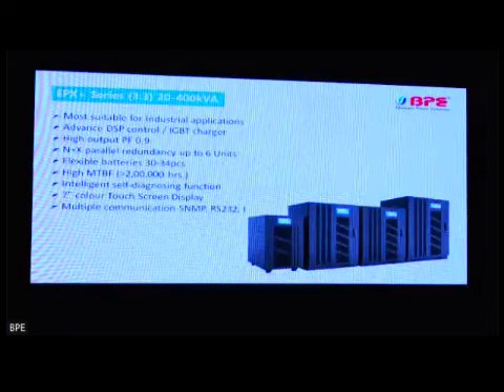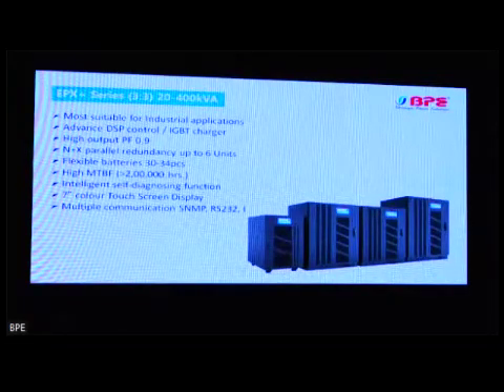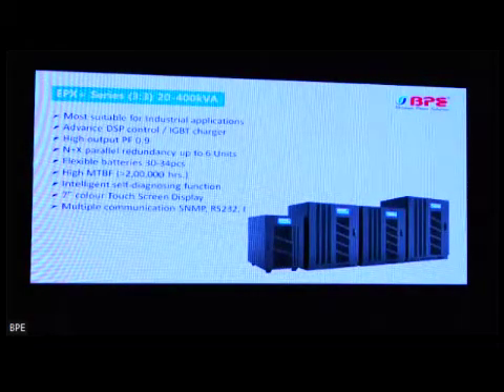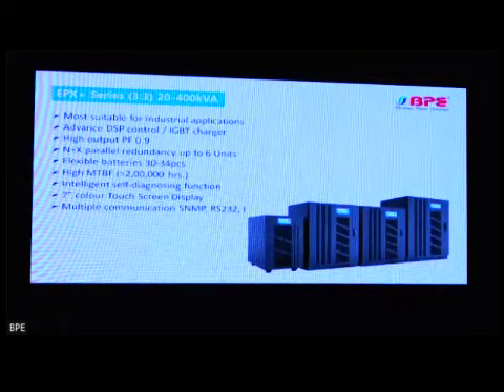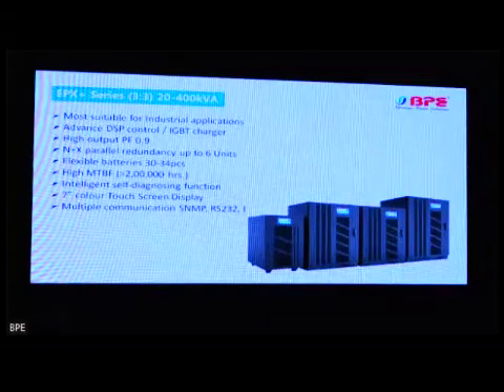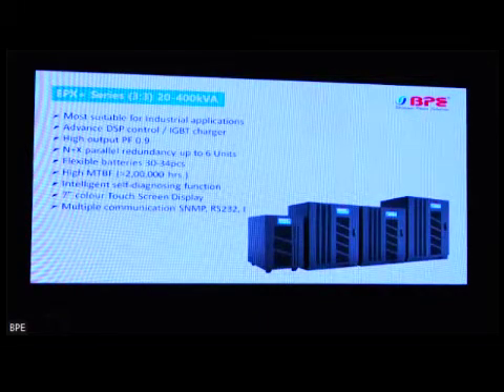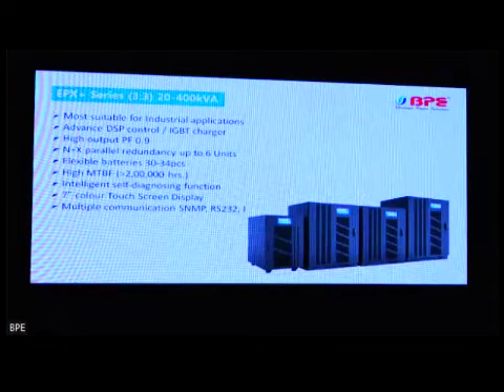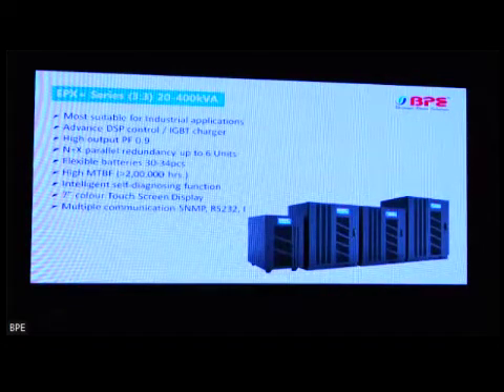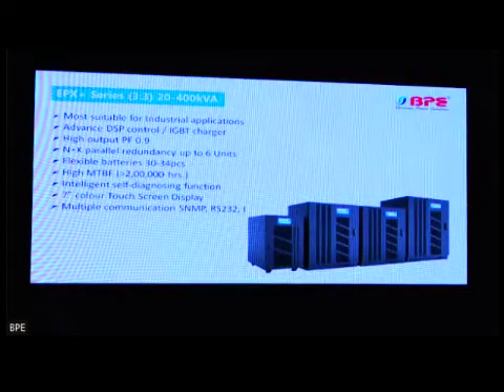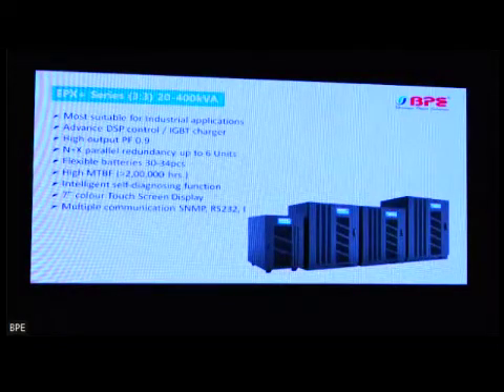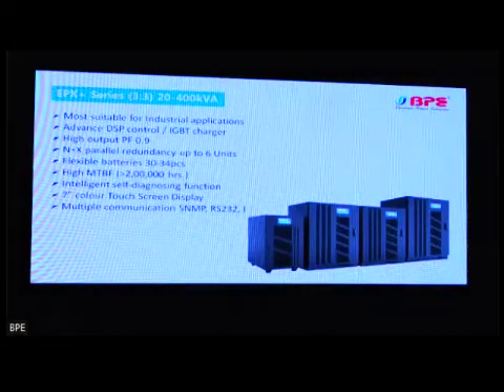Then we will have EPX Plus series starting from 20 kVA up to 400 kVA. This is most suitable for industrial applications. Advanced DSP and IGBT charger is there with high output power factor of 0.9. The MTBF of this UPS is very high, it's 2 lakh hours. And it has got 7-inch color touchscreen display with multiple communication SNMP RS232.